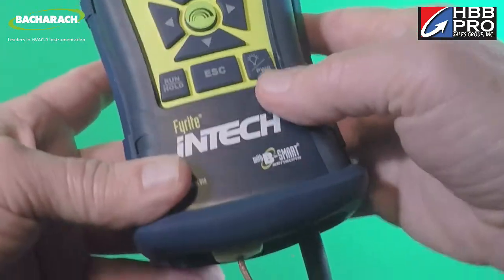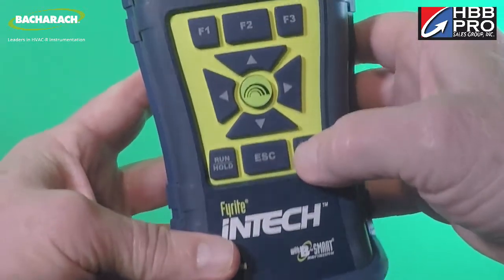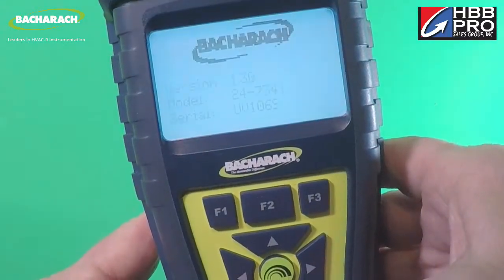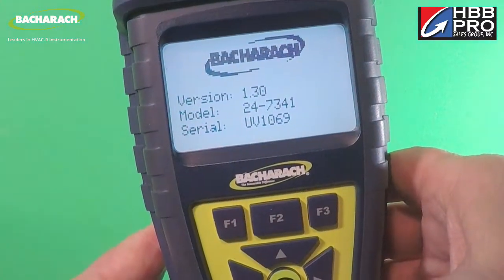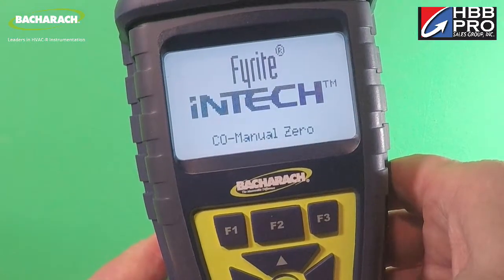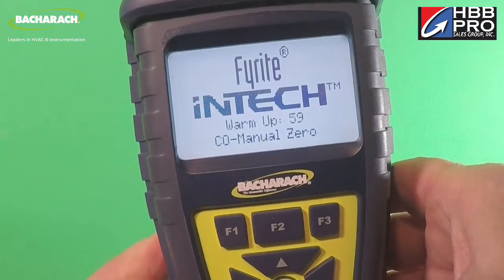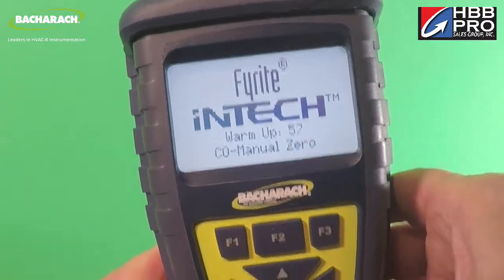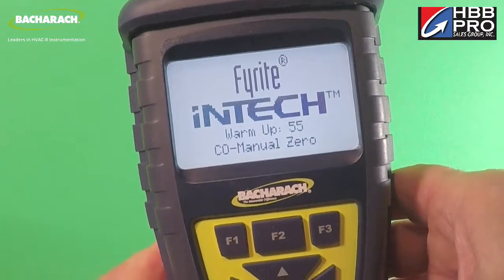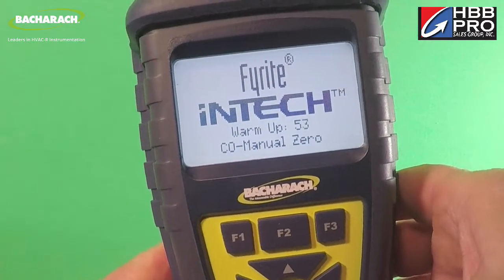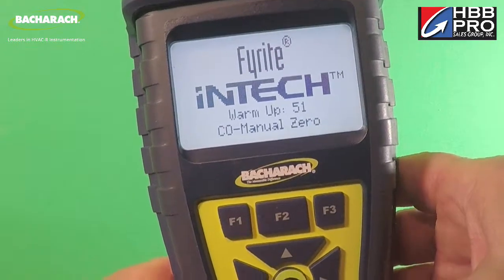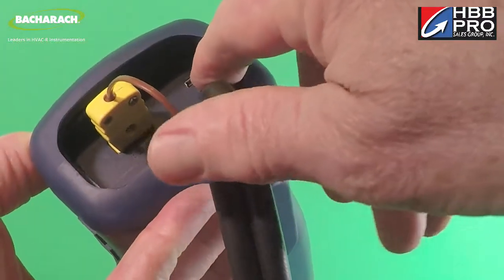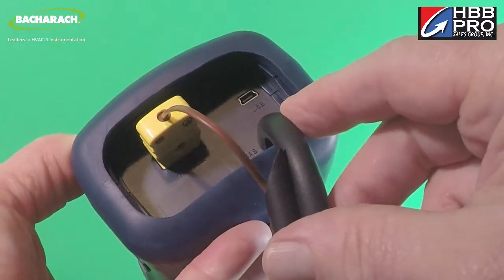Plug that in, and then to turn the instrument on, we'll press this button. And I want you to watch in the display. It comes up, you see it says version 1.30. That's something to take a look at. That's the most recent version of the firmware. If you have a previous version, you can go to Bacharach's website to download it and upgrade to the latest version. If you look at the bottom of the instrument there, you'll see a USB port. That's how you do it.